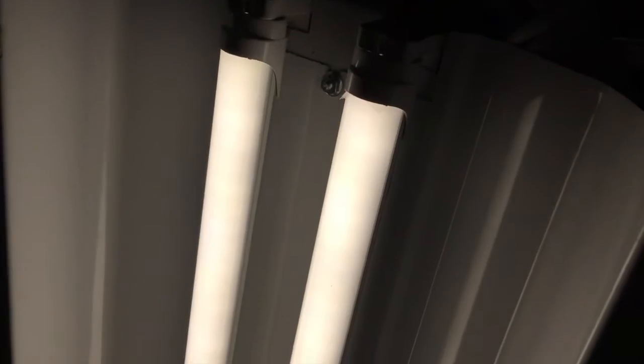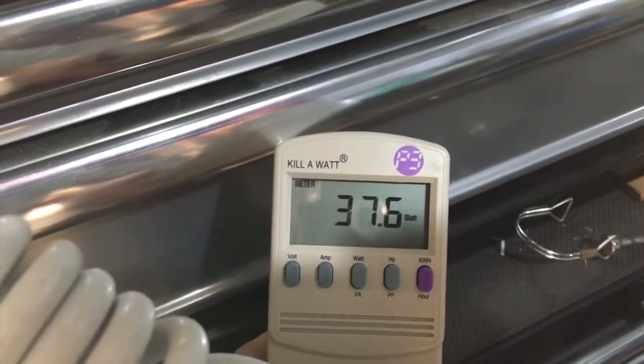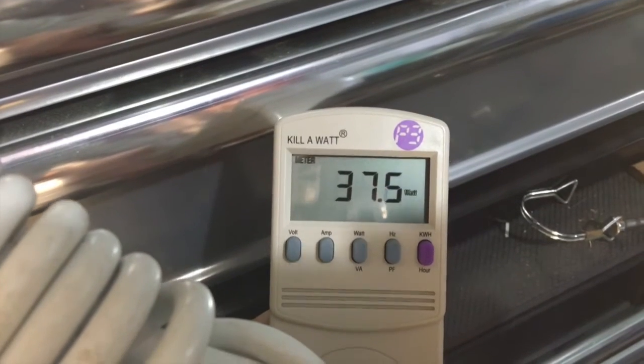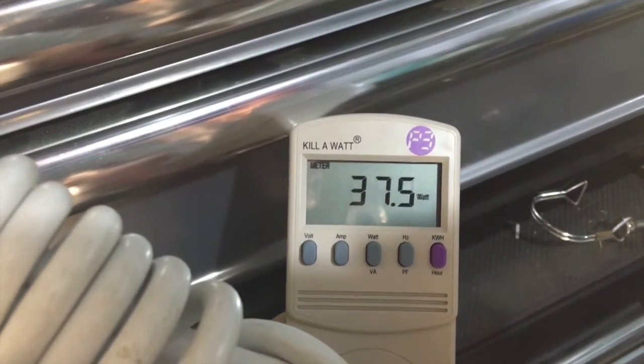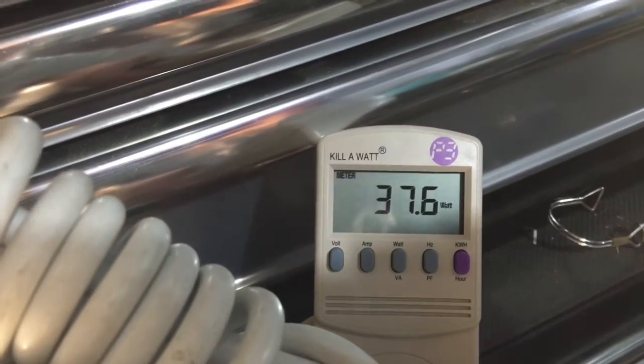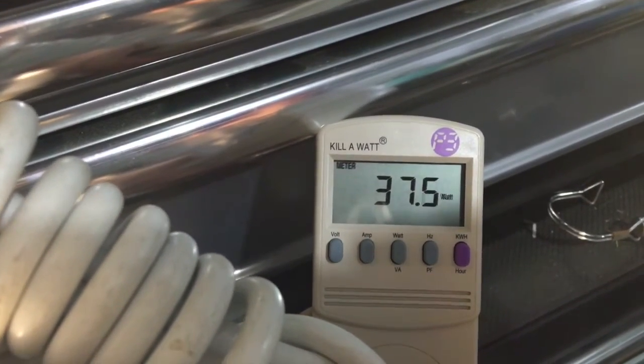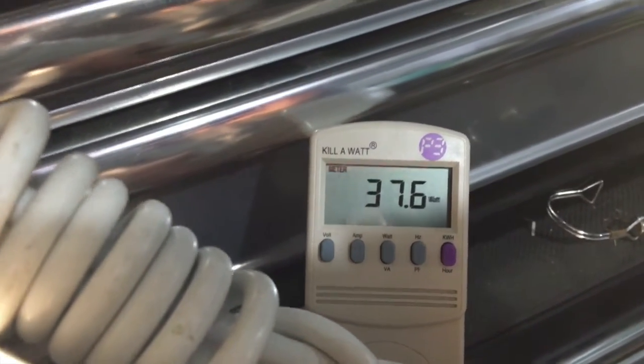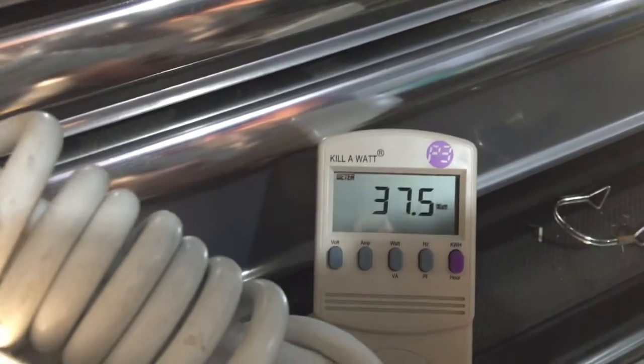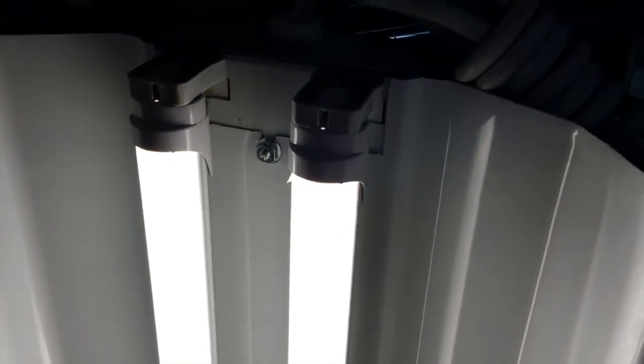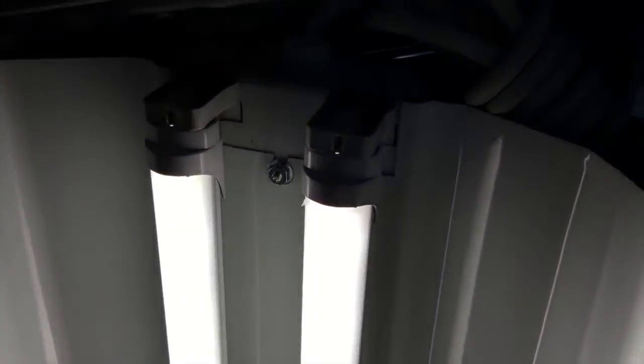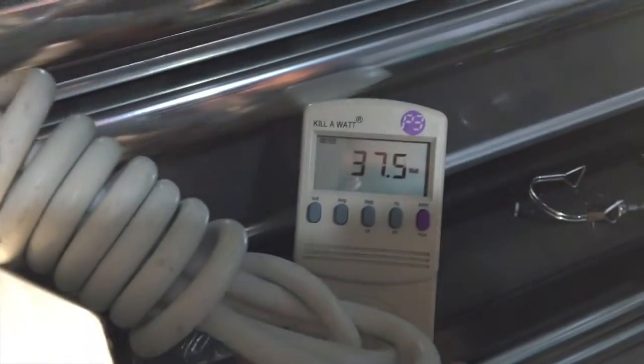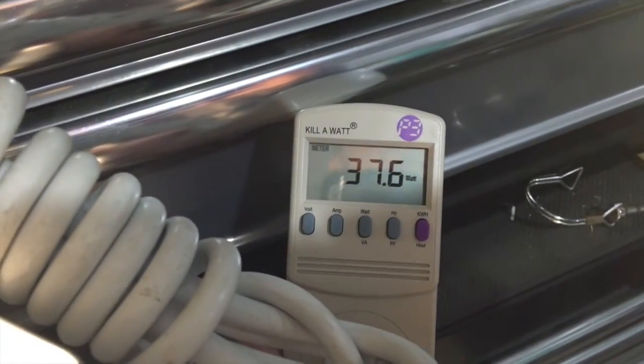It comes at about 4500K, which is not soft and it's not a warm white, it's not a cool white, it's kind of in between. I kind of like the 4000 range myself. But let's take a look at the Kill A Watt here. We can see this fixture right now is using 37.5, let's call it 38 watts of electricity, just under 38 watts. Now we're going to go to the other part of the room where I've got a very similar fixture. It's the same fixture, I've just painted the shroud a little different color. But it has fluorescent tubes and it has the ballast. So keep this number in mind, under 38 watts.